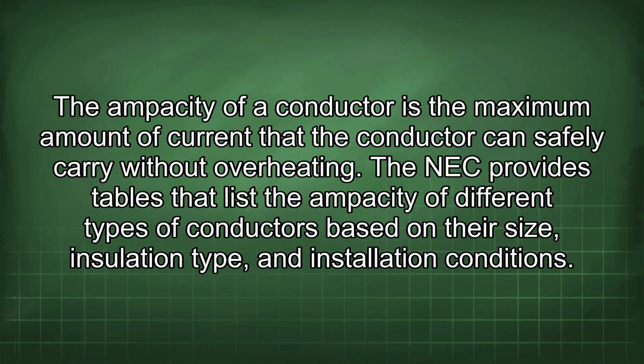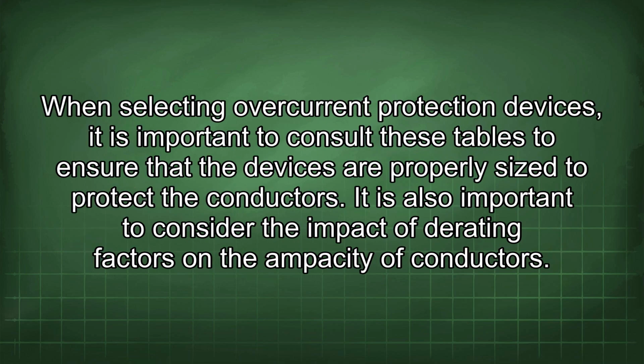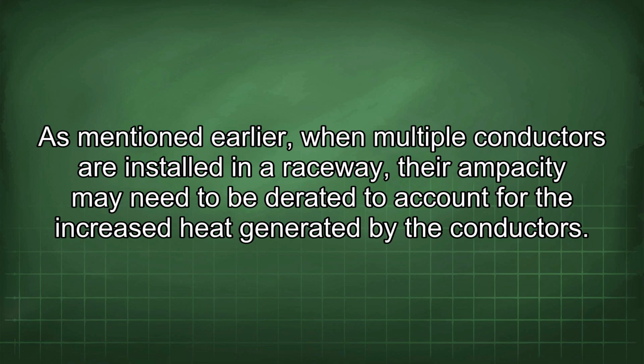The NEC provides tables that list the ampacity of different types of conductors based on their size, insulation type, and installation conditions. When selecting overcurrent protection devices, it is important to consult these tables to ensure that the devices are properly sized to protect the conductors. It is also important to consider the impact of derating factors on the ampacity of conductors. As mentioned earlier, when multiple conductors are installed in a raceway, their ampacity may need to be derated to account for the increased heat generated by the conductors.